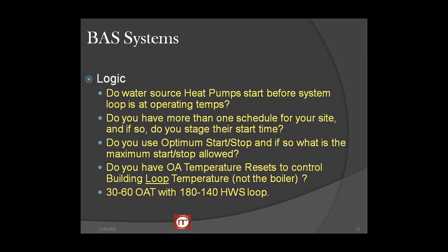Outdoor temperature resets to boiler loop controls. Can't say about your part of the country, but I can tell you about us here in eastern North Carolina. Something that you need to dial in your building. We use typically 30 to 60 degrees OAT, or outside ambient temperature. At 30 degrees, we'll deliver 180 degrees to the building. That's the design condition. At 60 degrees, we will reset the loop, not the boiler, to 140 degrees. The boiler's still doing 180, but if I only draw 140 off, the boiler does not run as much and effectively shuts down, and the building does not overheat as much.